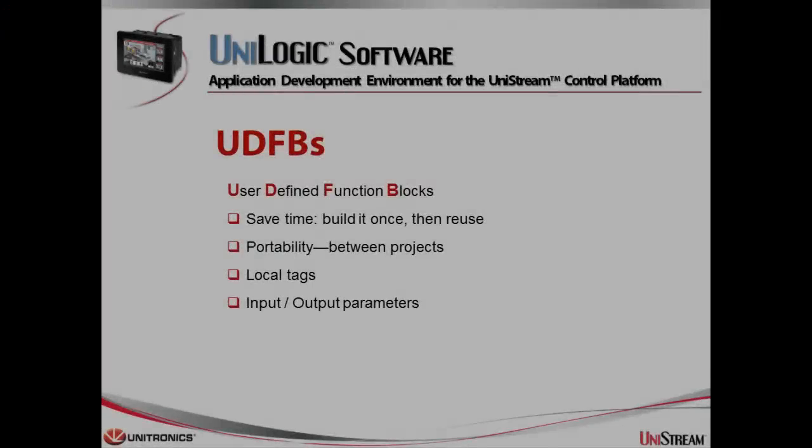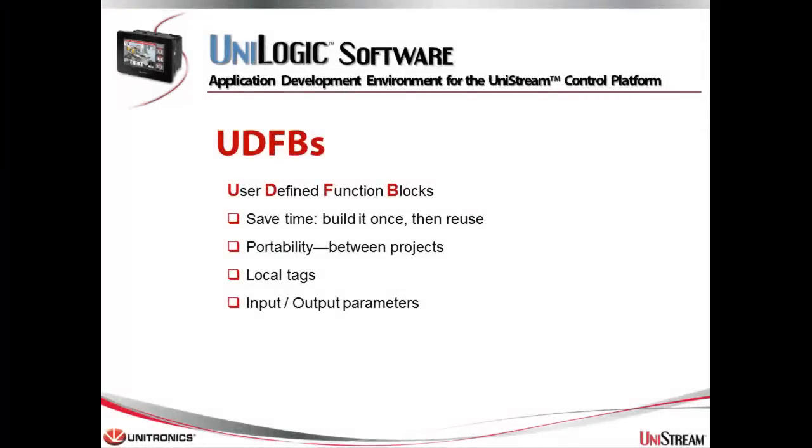User defined function blocks or UDFBs will save you a lot of programming time. This feature enables you to build your own functions and then reuse them. You can also export and import them between projects. Use local tags with UDFBs to avoid data conflicts.